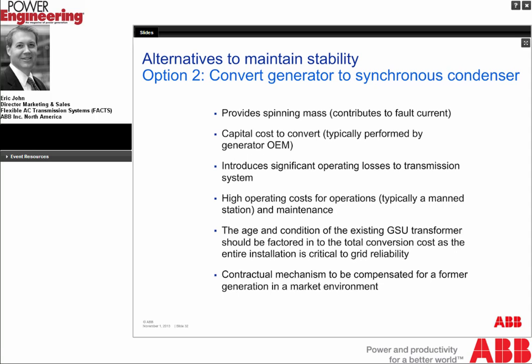The next thing to consider is the capital cost of the conversion. Normally there is a cost, and it can be fairly substantial, a 7 or 8-figure cost to make the capital improvement, which can involve rewinding the generator, replacing the controls, upgrading the excitation system of the generator, and often the generator owner is captive to the OEM of the generator unit to perform that work.